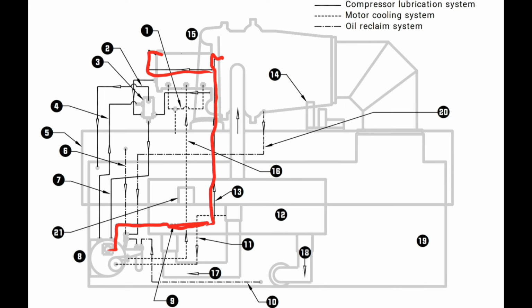The reason this is so critical and so important is because that oil at that temperature has a very specific viscosity, okay? And so it's what it's designed to, its lubricating parameters, everything that we need it to do and be in its life revolves around that set temperature range. Anything outside of that, it starts to become too thin or too thick in order to do the job we're asking of it. If everything was just standard ball bearing, it wouldn't be as critical, and many centrifugals use what are known as journal bearings, okay?